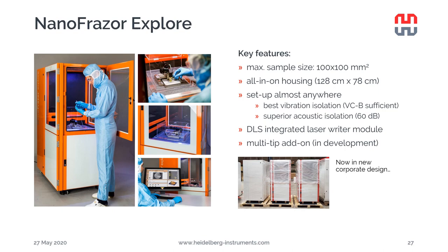NanoFrazor Explore can pattern samples as large as 100 mm by 100 mm. It has one housing for the writing head, electronics, and vibration isolation. There is a small compartment to keep your gas bottle to provide the gas flow for the environment box. The housing provides very good acoustic isolation. As long as the acoustic noise in your lab is less than 60 dB, Explore can properly operate. There are only two cables coming out of the system. One is the power cable and the other is a signal cable to the computer.